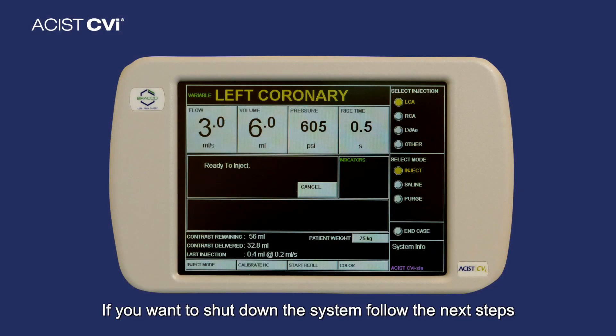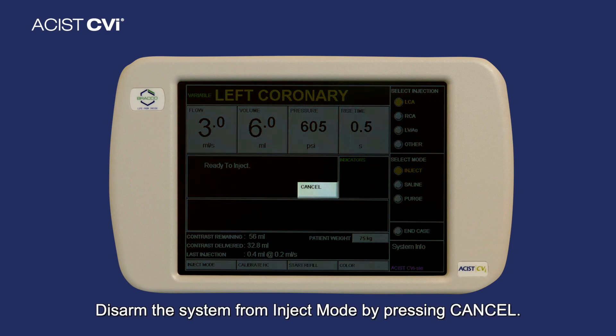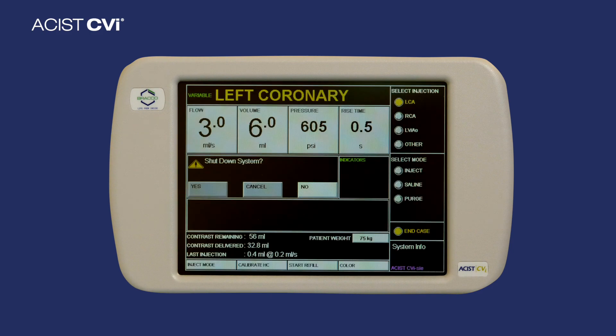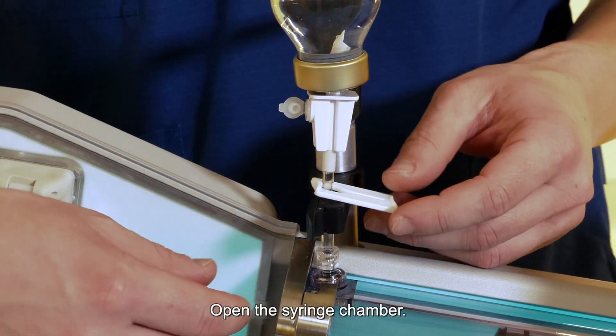To shut down the system, follow the next steps. Step 1: Disarm the system from Inject Mode by pressing Cancel. Step 2: Press End Case, then OK. Step 3: Select Yes when prompted to shut down.